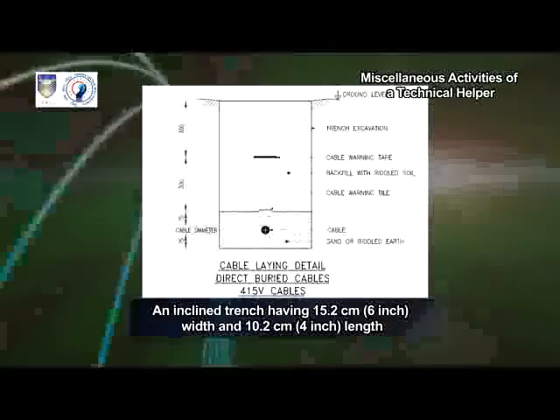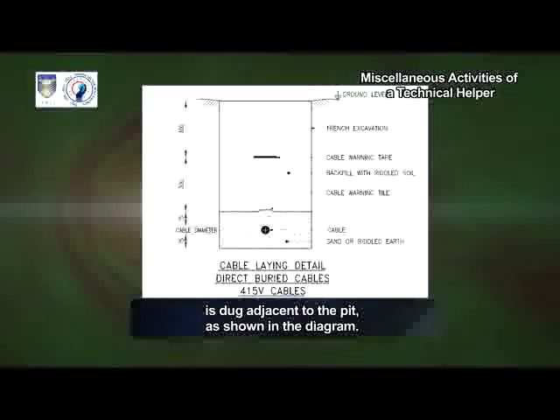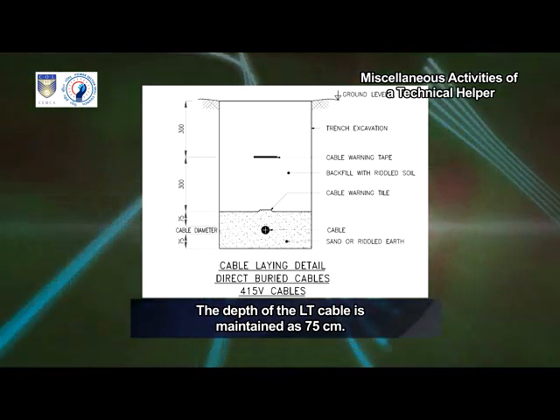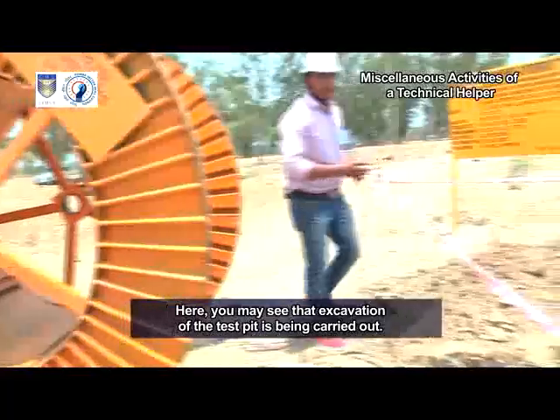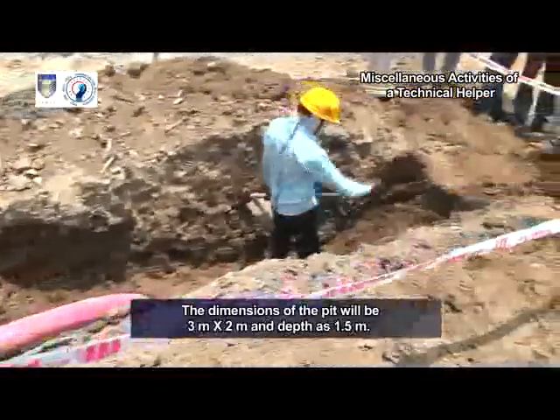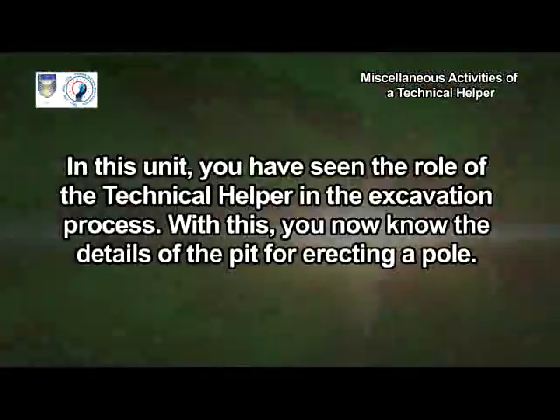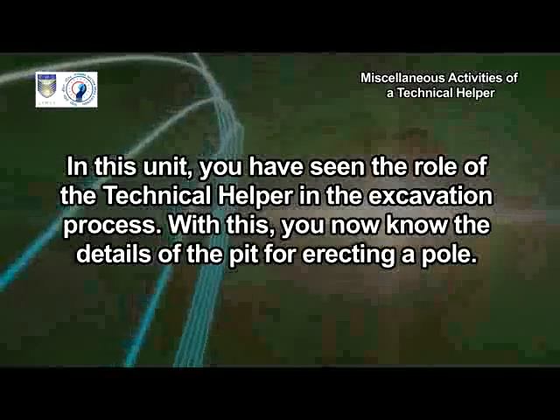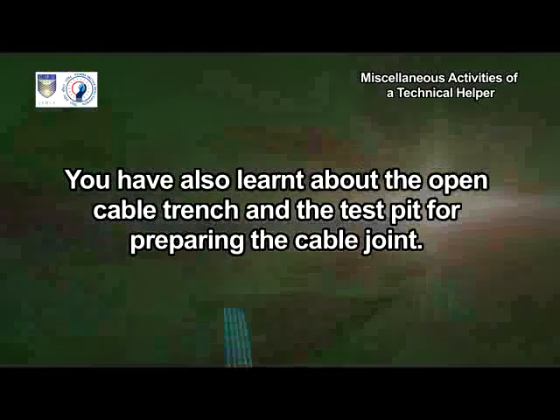An inclined trench having 15.2 centimeters (6 inch) width and 10.2 centimeters (4 inch) length is dug adjacent to the pit, as shown in the diagram. The depth of the LT cable is maintained as 75 centimeters. Excavation of the test pit is also being carried out, where the HT cable will be prepared straight through the joint. The dimensions of the pit will be 3 meters by 2 meters and depth as 1.5 meters. You now know the details of the pit for erecting a pole, the open cable trench and the test pit for preparing the cable joint.